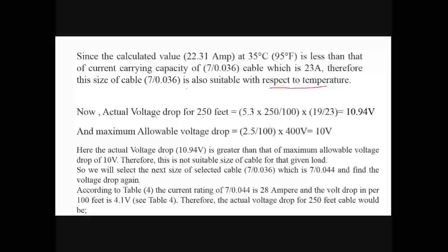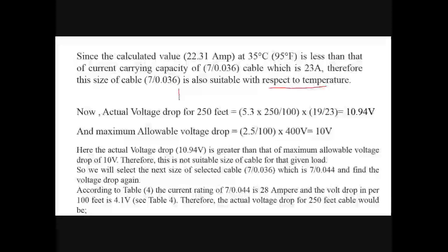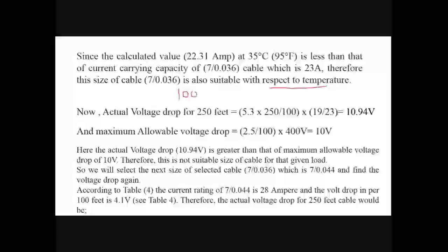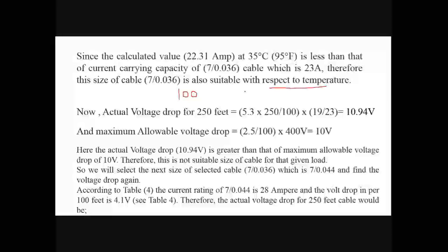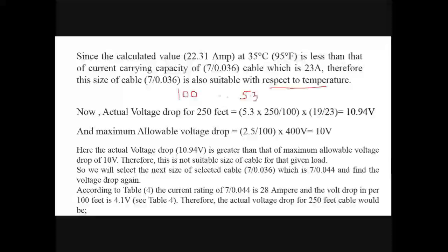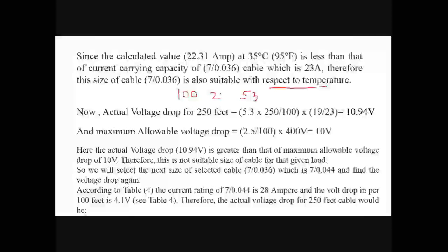But we have to take the actual voltage drop. What is the formula? The formula is very simple. They have given the value for 100 feet. For 100 feet, they have given the value as 5.3 volt. And what we have to find out? We have to find out for 250 feet.